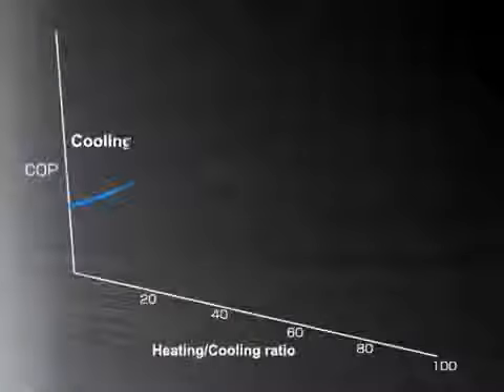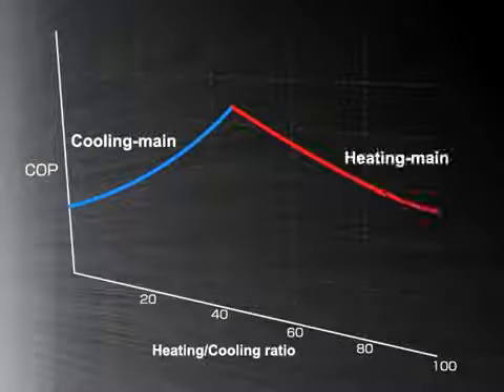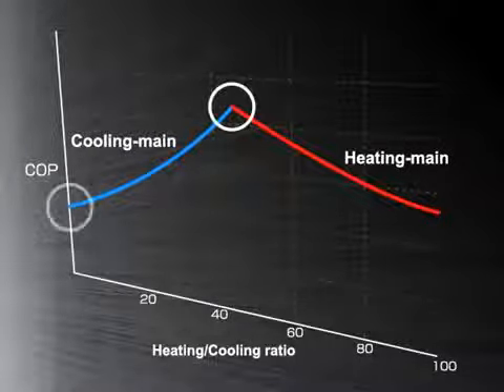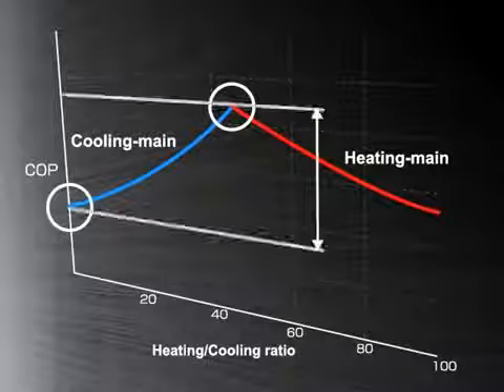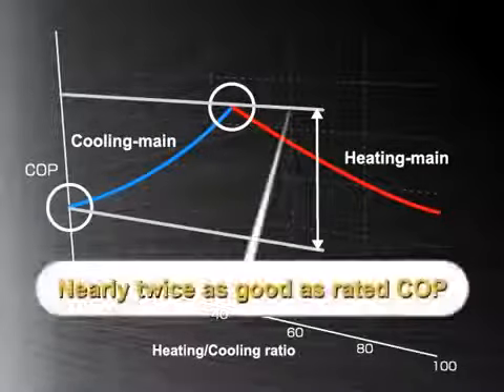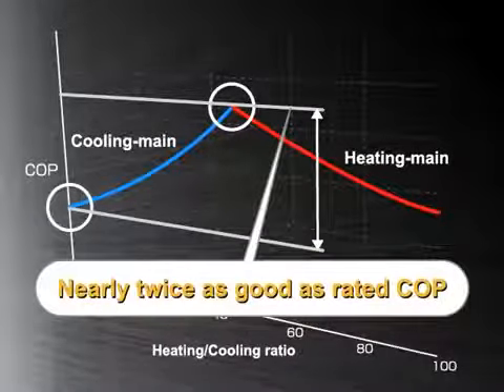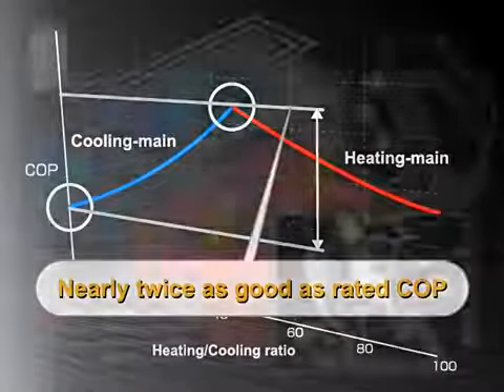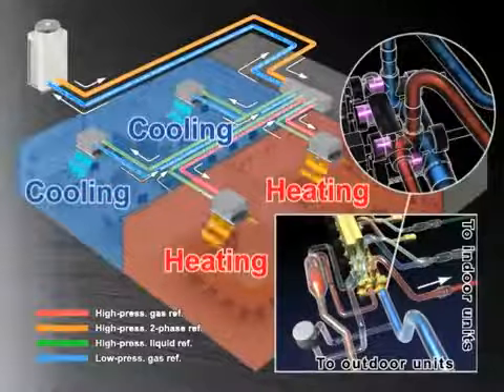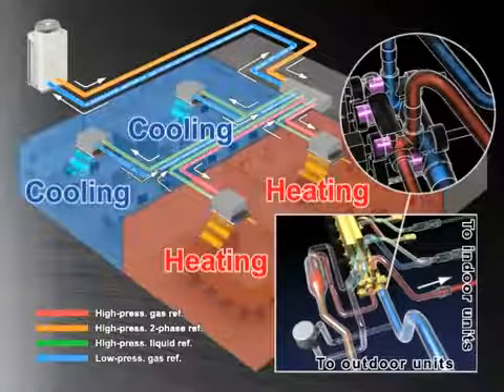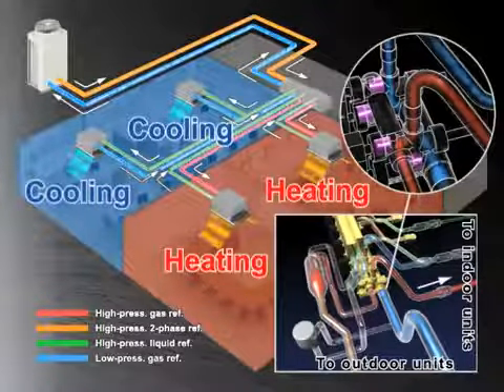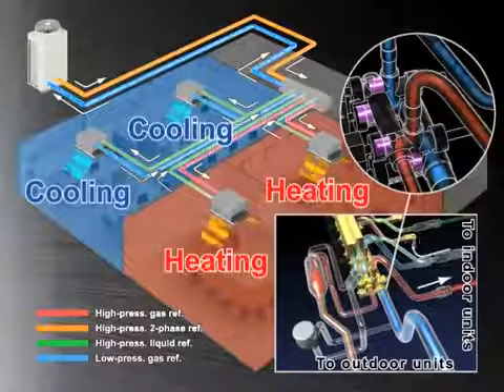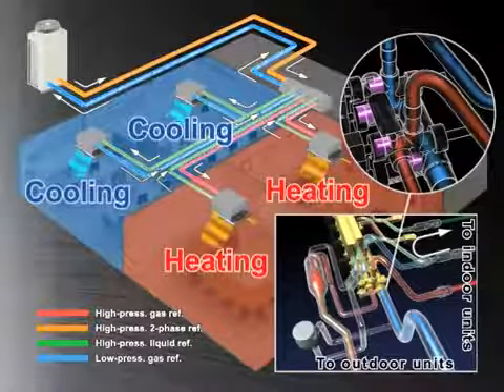Putting it simply, waste heat from heating operation is reused for cooling operation, and the more frequently cooling and heating simultaneous operation is carried out, the higher the energy-saving effect becomes. The reusing of waste heat is applied to air-to-water system. It utilizes waste heat from cooling for heating operation, which provides hot water.